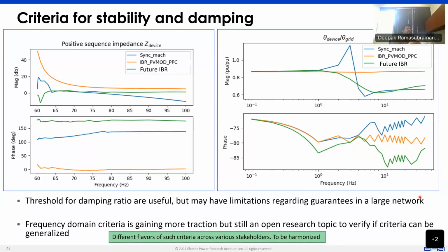We might have to go down into aspects of frequency domain characteristics, which have been reported also in other parts of the industry, and we have started seeing some of this come to the forefront. Things like the impedance of the device as seen around the fundamental frequency, or in a short range of frequencies around the fundamental frequency. We see that a conventional IBR plant would have a higher impedance value. A synchronous machine plant has a slightly lower impedance value. A future inverter plant has a yet lower impedance value. And if you plot an enhanced IBR response on this, you would see that it lies in between the synchronous machine behavior and the future IBR behavior.